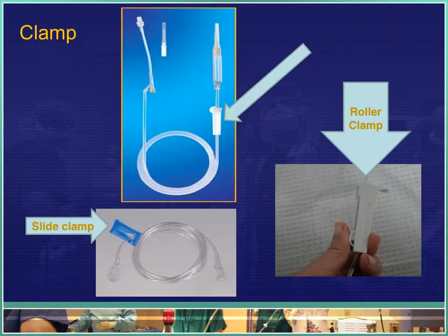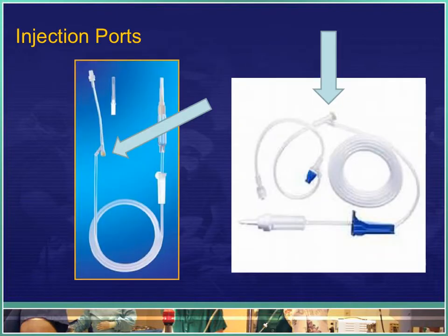The flow clamp control device operates on the principle of compression of the tubing wall. The roller clamp is found on all the tubing as the clamp is tightened. Some sets also include a slide or pinch clamp that often is used as on-off controls and are never used to regulate flow. Injection ports serve as an access into the tubing and are located at various points along the administration set. Usually the ports are used for medication administration.